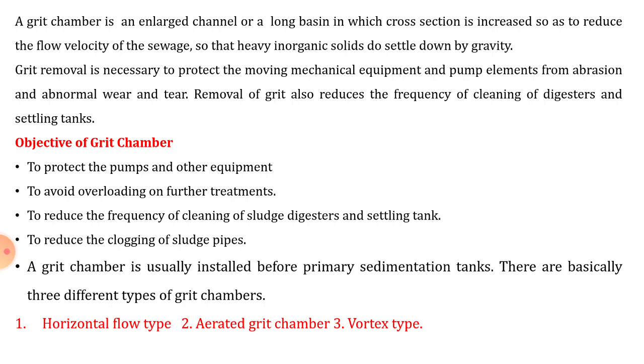Grit removal is necessary to protect moving mechanical equipment and pump elements from abrasion. If grit is present in wastewater transferred directly to the primary treatment plant, it will cause abrasion of mechanical equipment and abnormal wear and tear. Removal of grit also reduces the frequency of cleaning of digesters and settling tanks. The objectives of the grit chamber are: to protect pumps and equipment, to avoid overloading on further treatments, to reduce cleaning frequency of sludge digesters and settling tanks, and to reduce clogging of sludge pipes. The grit chamber is usually installed before the primary sedimentation tank.